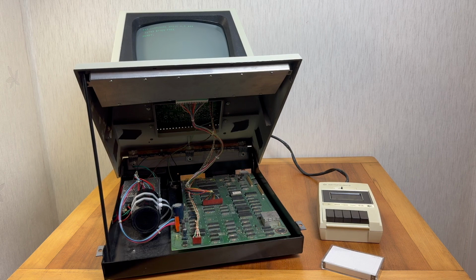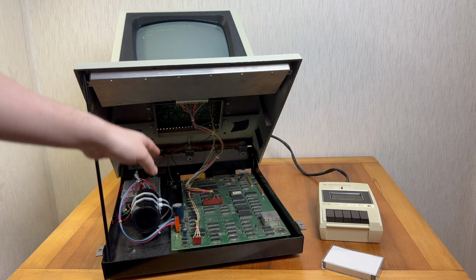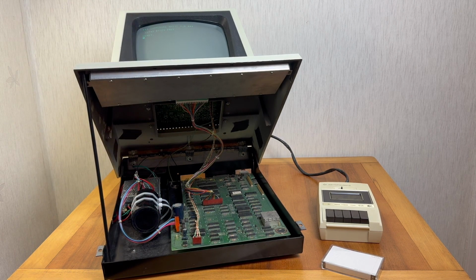I've modified the supply to provide the required voltages via the existing header here and via the existing cables into the monitor cabinet. This means that power regulation is carried out via the existing circuitry on the main board. The supply itself is retained in place using a 3D printed bracket, affixed using the original fixing screws. This approach was taken to ensure that all of the changes I've made are as reversible as possible and allow the owner to revert back to the original transformer if they choose to do so in future.